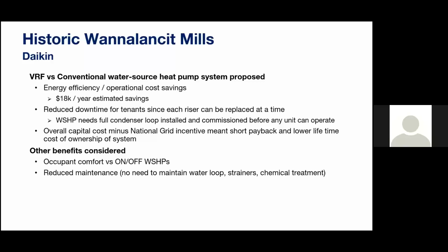Then just comparing a few additional things, the VRF systems have variable speed operation, which improves the occupant comfort versus those on-off water source heat pumps, which could easily overcool or overheat the space, which is what Jason went over. With them being a single stage system as well, it could mean that they would be turning off and on more frequently, which would be inefficient. And then reduced maintenance on the VRF systems without the need to maintain the water loop, which would need strainers, chemical treatment for the water, and pumps and all things like that.